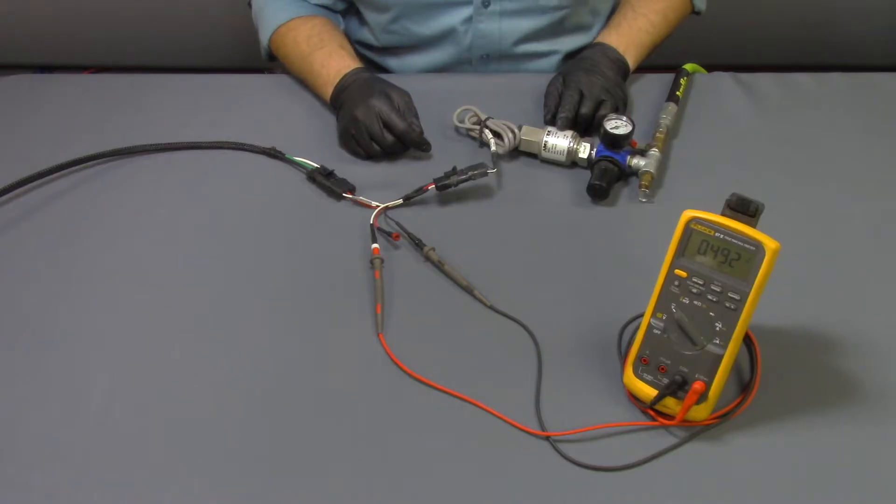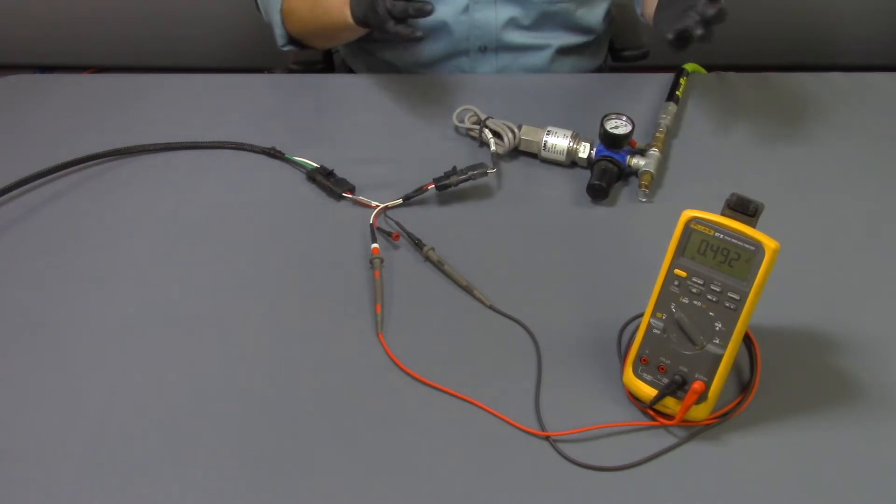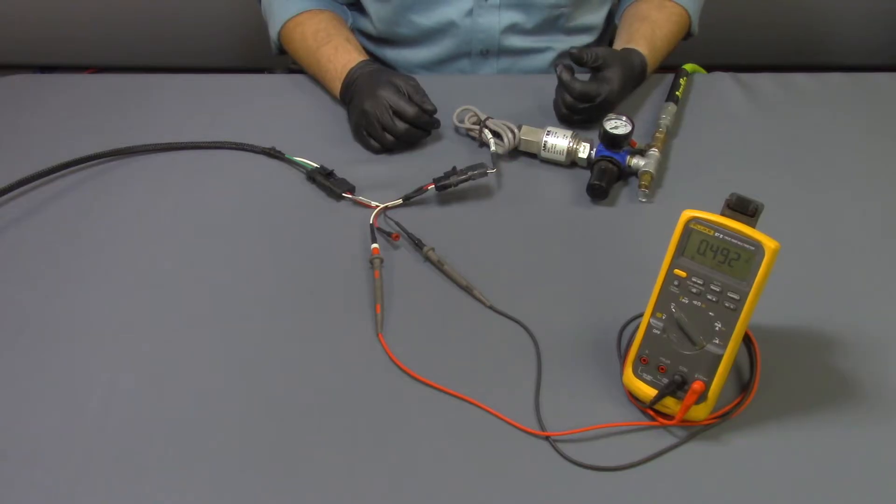Now this is a 0.5 to 5 volt pressure sensor, 0 to 100 psi. So at 0.5 volts we should be right around 0 psi. At 100 psi we'll be at 5 volts and in between that is a range between 0.5 and 5. So around 50 psi, which is halfway, we should see 2.75 volts.